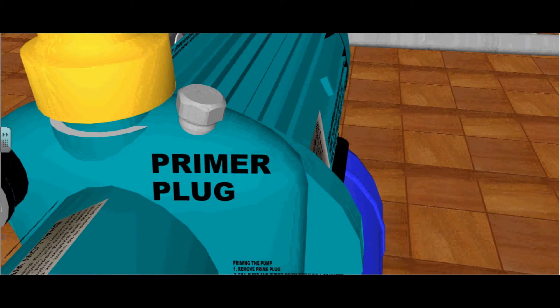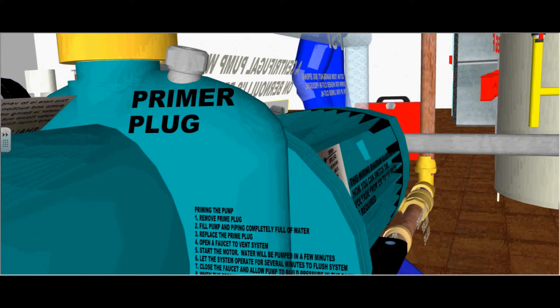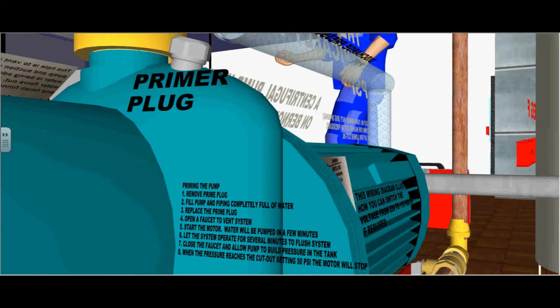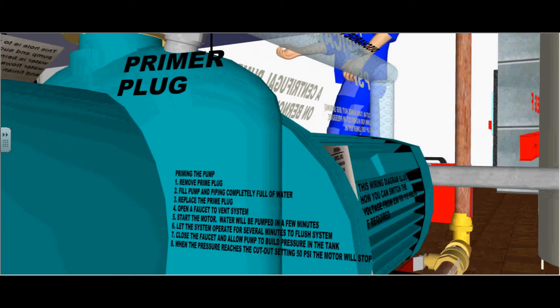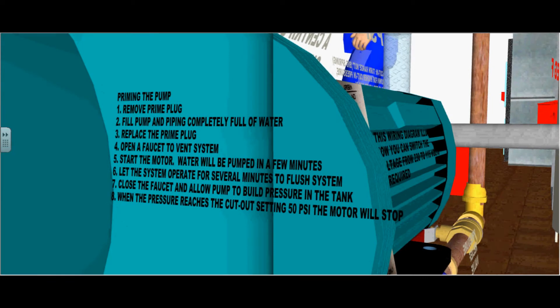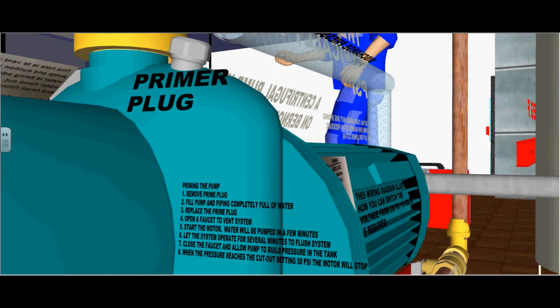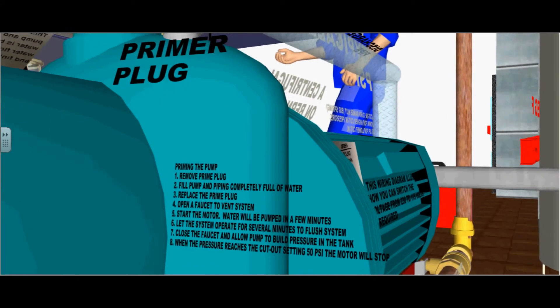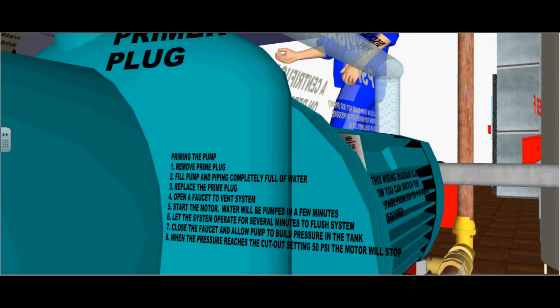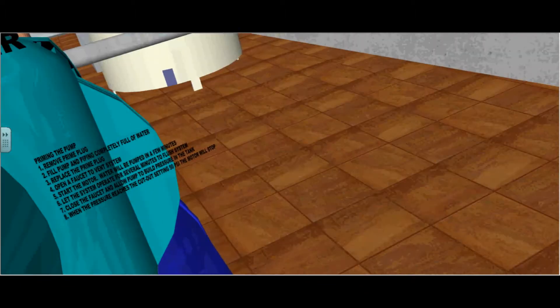Here is the primer plug. So if you want to prime your pump on new installation, you remove the prime plug, fill the pump and piping completely full of water, replace the prime plug, open a faucet to vent the system, start the motor. Water will be pumped in a few minutes. Let the system operate for several minutes to flush the system. Close the faucet and allow the pump to build up pressure in the tank. When the pressure reaches the cutout switch or cutout setting of 50 psi, the motor will stop.